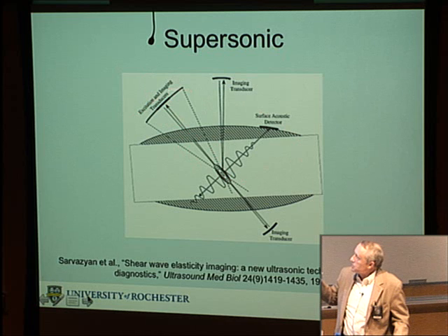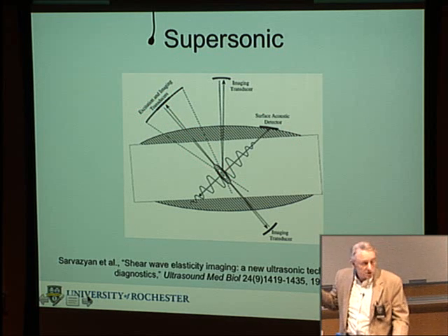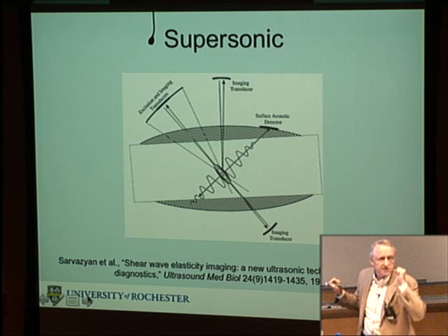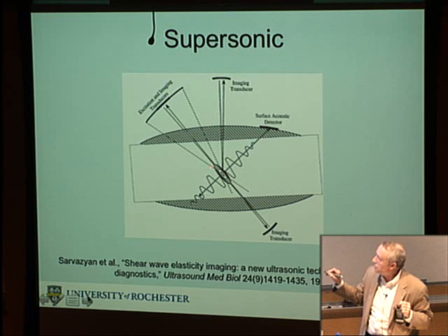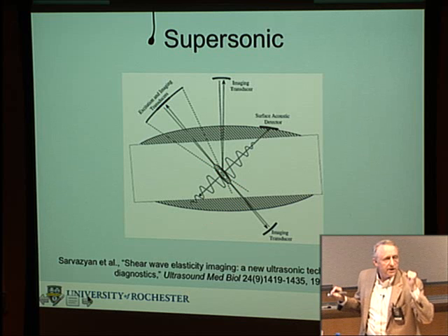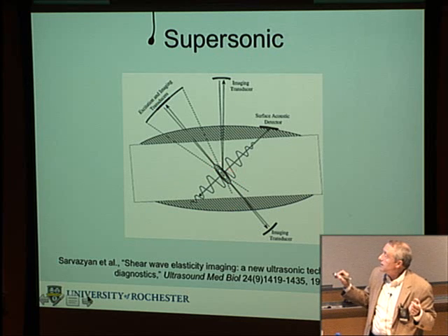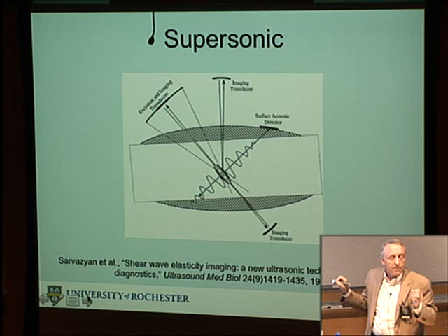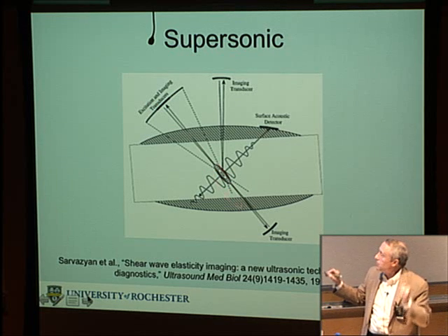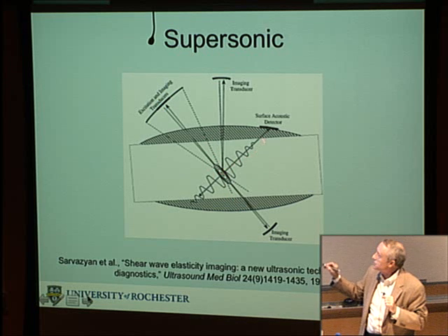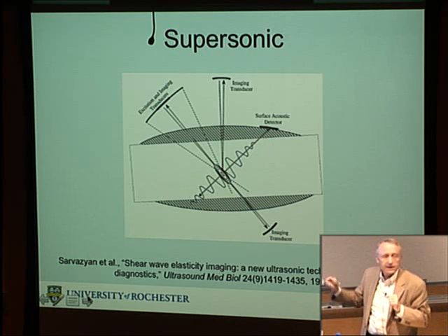Well, here's an ultrasound transducer, and as I mentioned before, if you turn it on high intensity for, let's say, 10 milliseconds, at the focal region you're going to make a little radiation force. So it's like a little force acting on this region of tissue. Now, ARFI monitored the displacement and then the recovery of this region. But what also happens, if you give this a quick enough bang, you actually produce a shear wave that propagates out to the right and left.